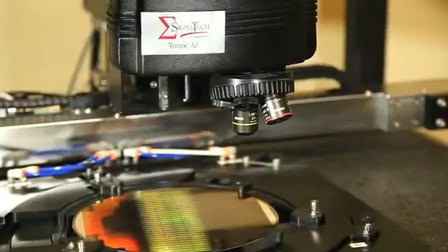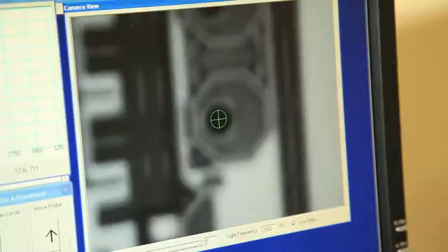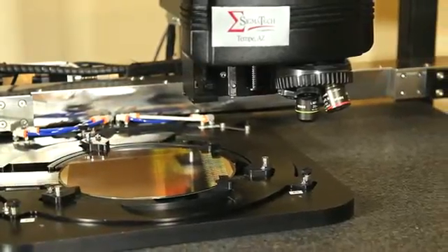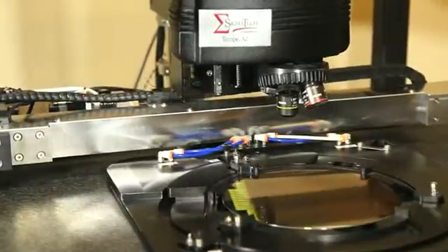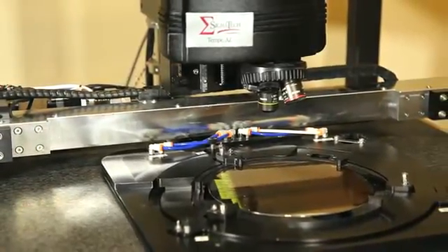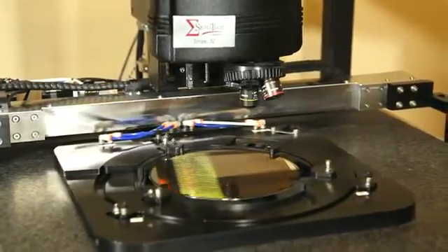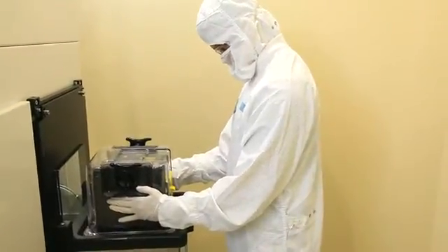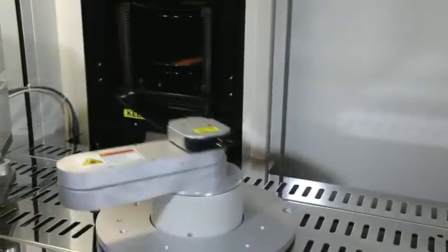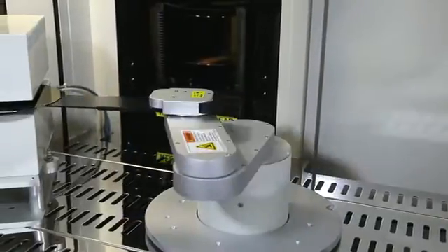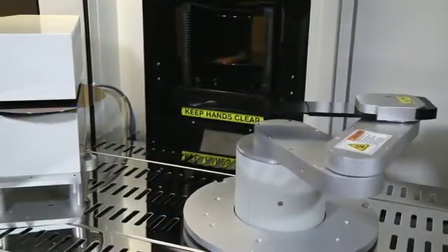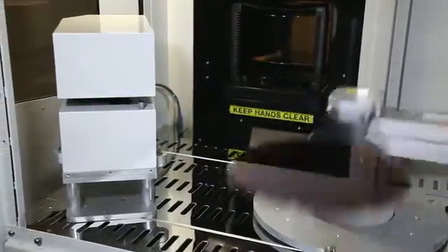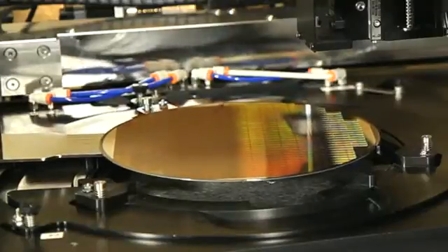The UltraMap-TSV incorporates a vision system with auto-fiducial locating and pattern recognition. In combination with our unique frictionless stage with air-bearing support, the accurate, high-throughput, non-destructive measurement of TSV features can be routinely realized. The UltraMap-TSV system is offered in a Class 1 compatible configuration and can also be provided with FOUP or SMIF loaders. If desired, the system can also be configured to measure wafer bow, warp, and thickness, in addition to measuring TSV depth uniformity, all on the same platform.